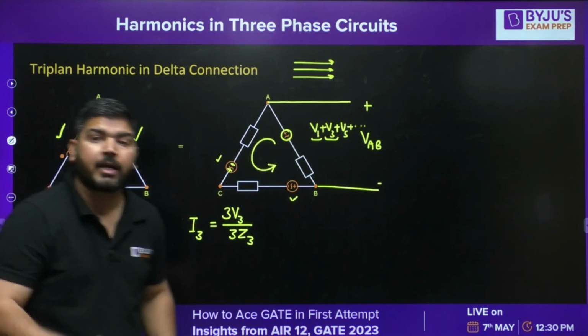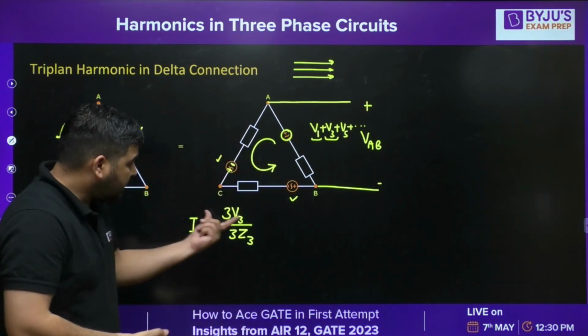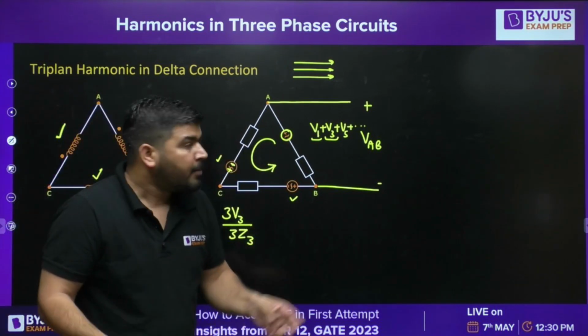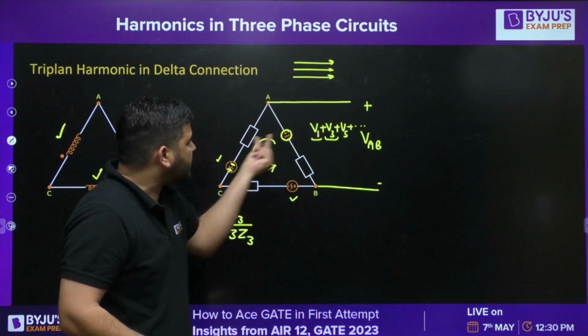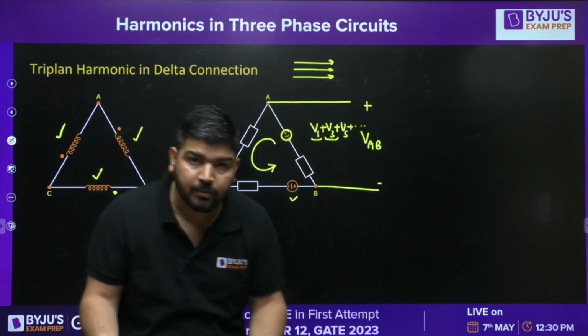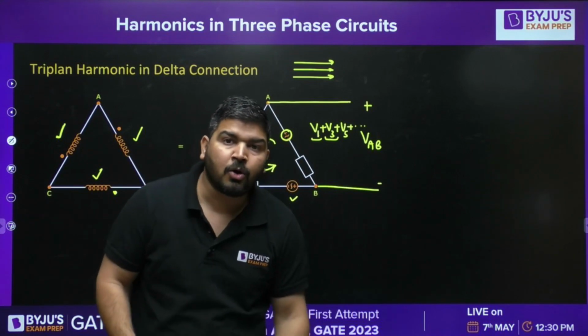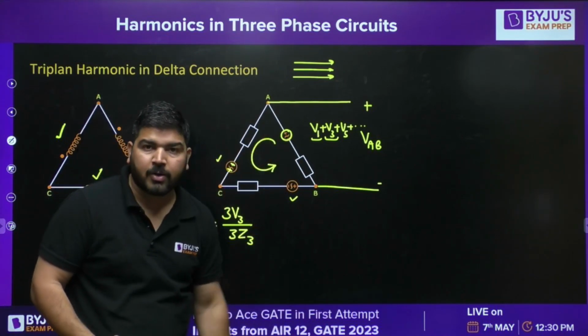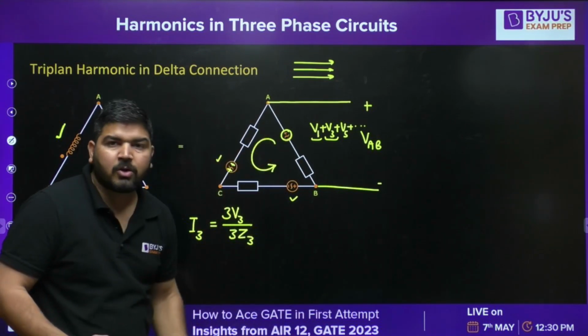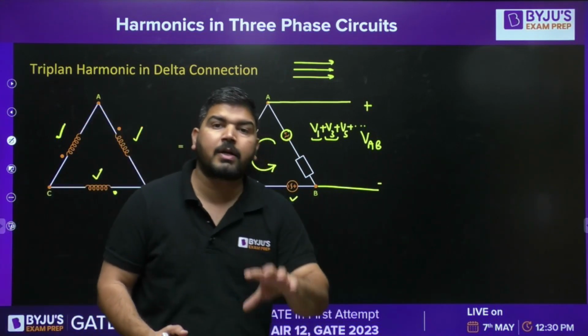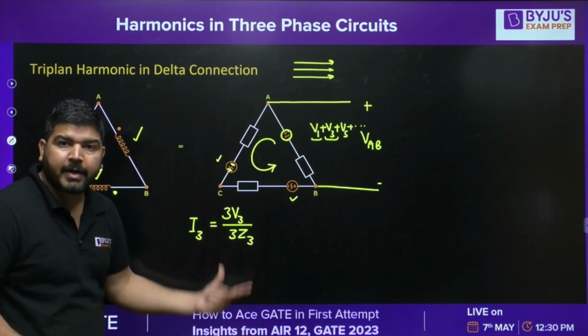Similarly, due to the ninth harmonic. Why is there no circulating current due to the fundamental? Because if you add the fundamental component of this phase and this phase, the sum will be zero. That's why there will be no circulating current due to the fundamental component. The circulating current occurs only because of the third, ninth, fifteenth—all triplen harmonics will produce circulating current.